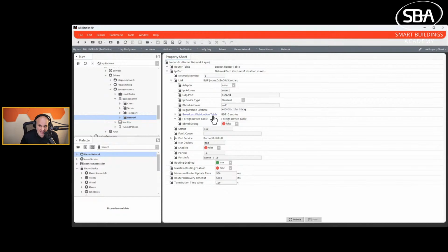As soon as we build that, which we don't build that, the discovery process builds it, it's programmatic. But once that's built, then we actually switch over to unicast and multicast messages that are managed by the BVLCs, the BACnet virtual links, and the APDUs and NPDUs. I know this all is confusing. We're going to look at Wireshark and it'll make a little bit more sense.